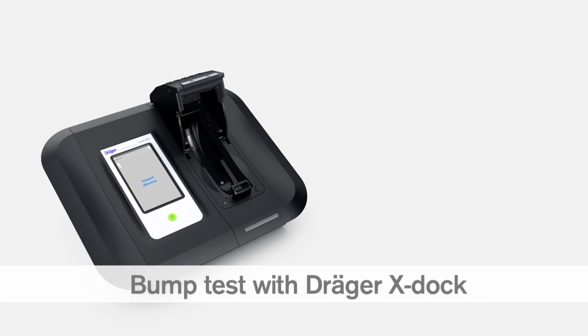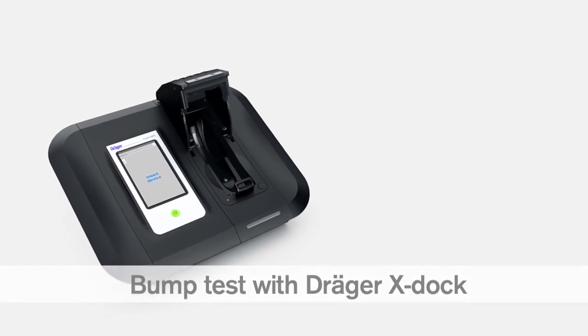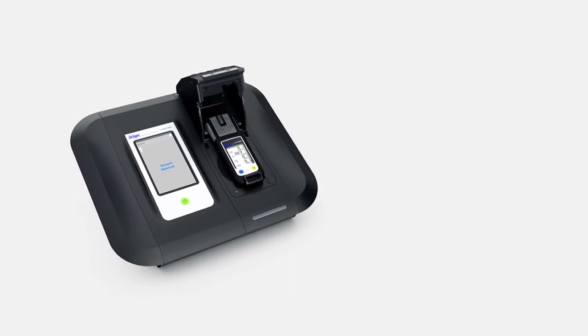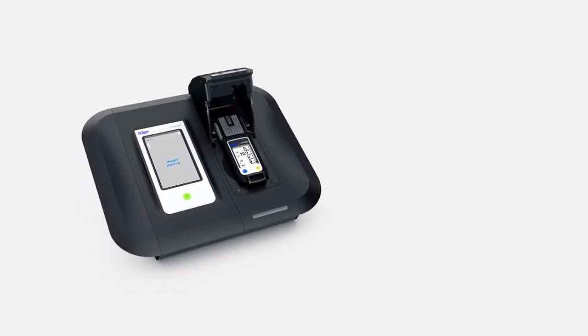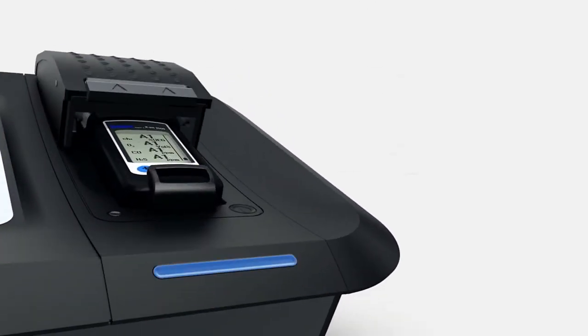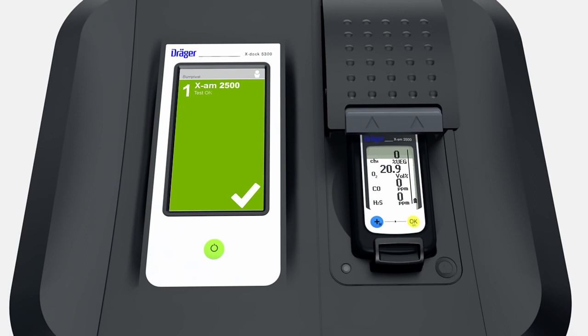You can also carry out a bump test with a Dräger X-dock station. Place an instrument inside the module. When you do so for the very first time, the Dräger X-dock recognizes the device and logs it in its integrated database. The LED strip flashes blue. When the LED changes to green, the test has been completed successfully. The X-dock screen also turns green — touch it to obtain additional information on the test results.